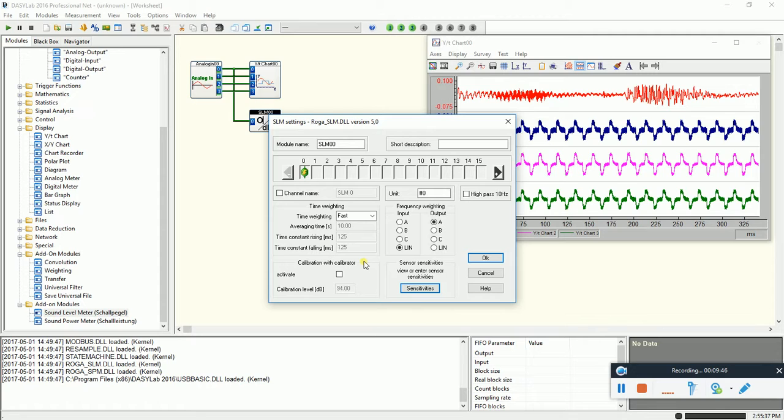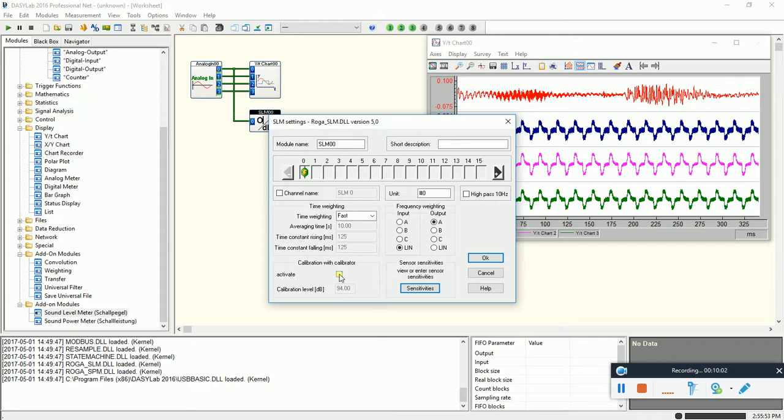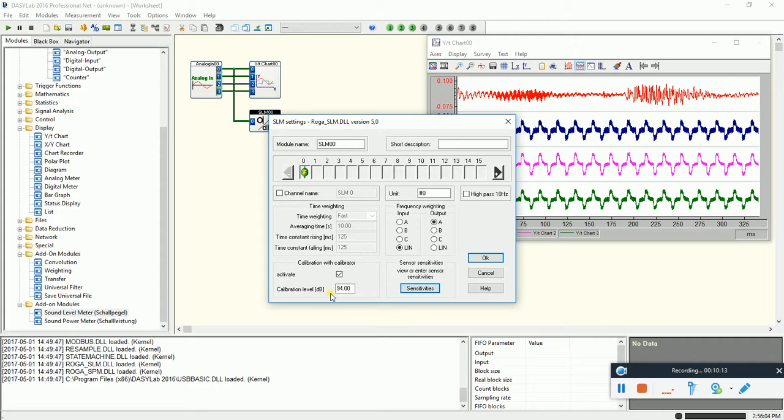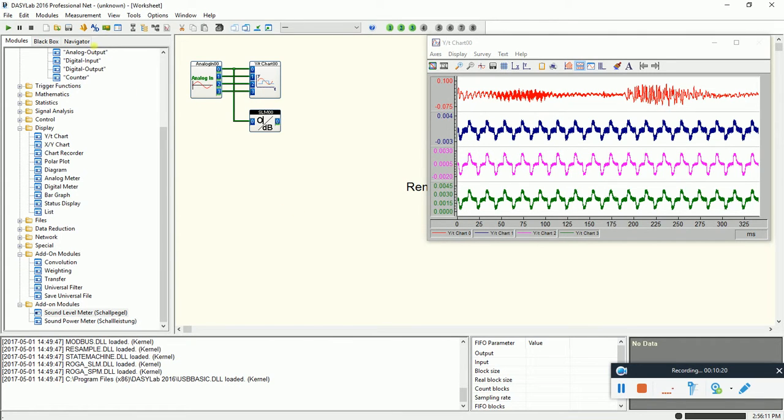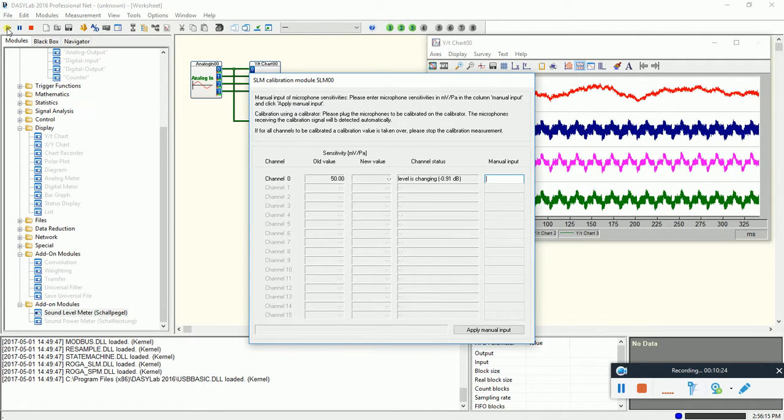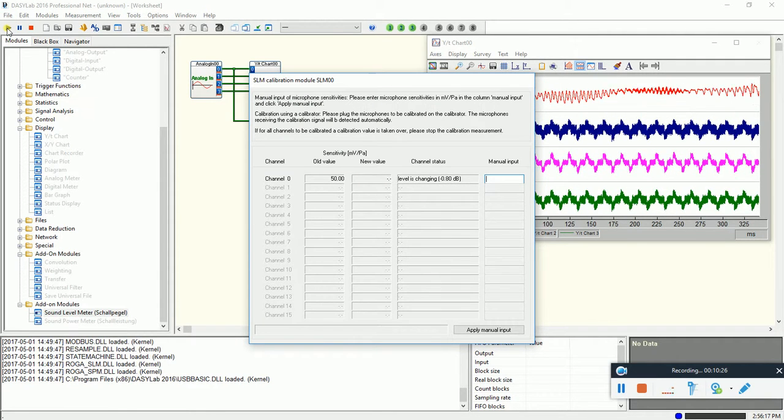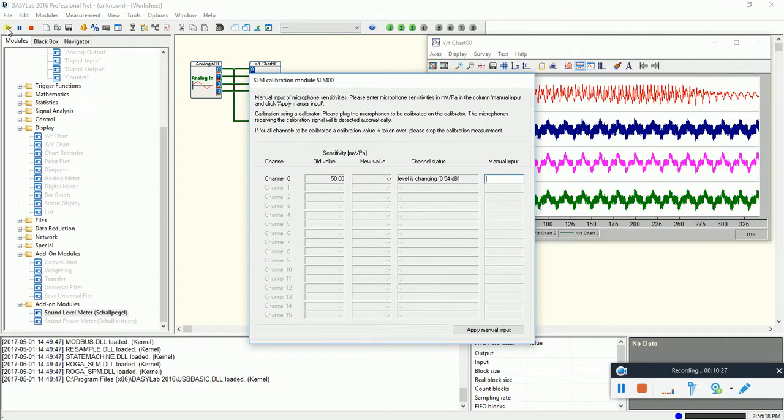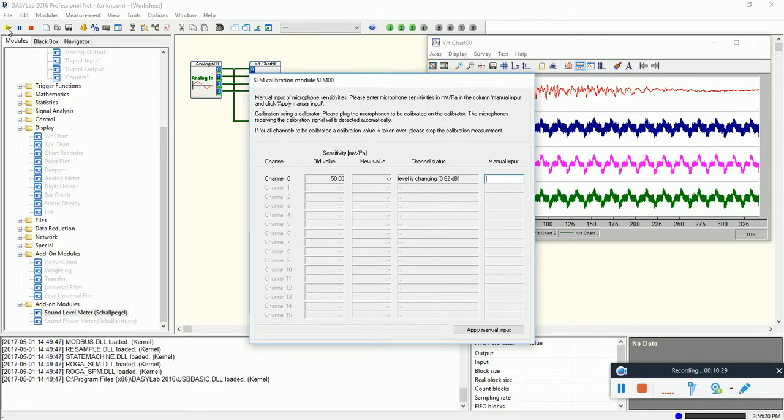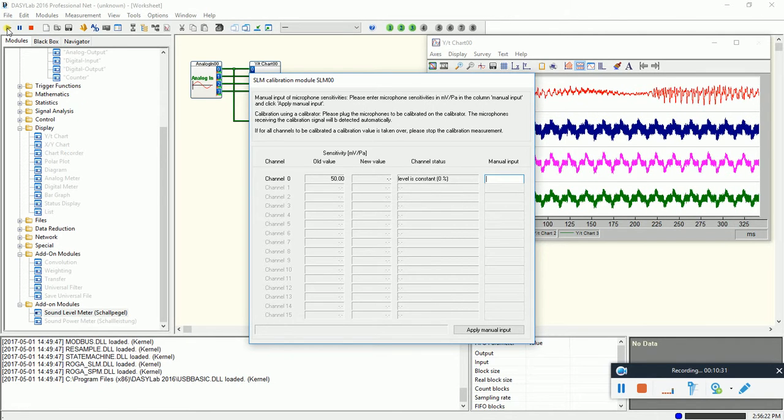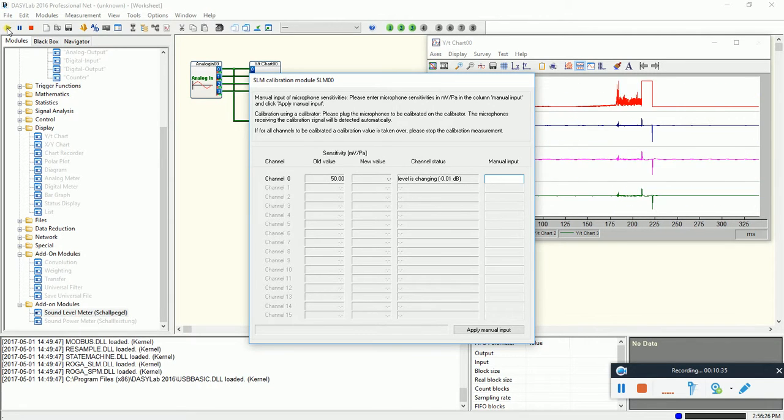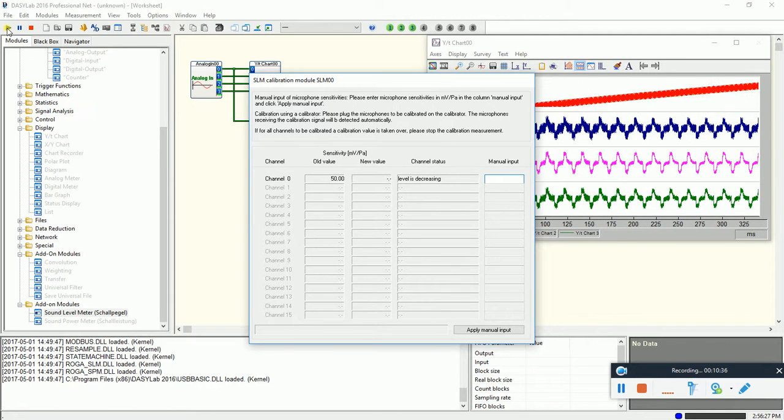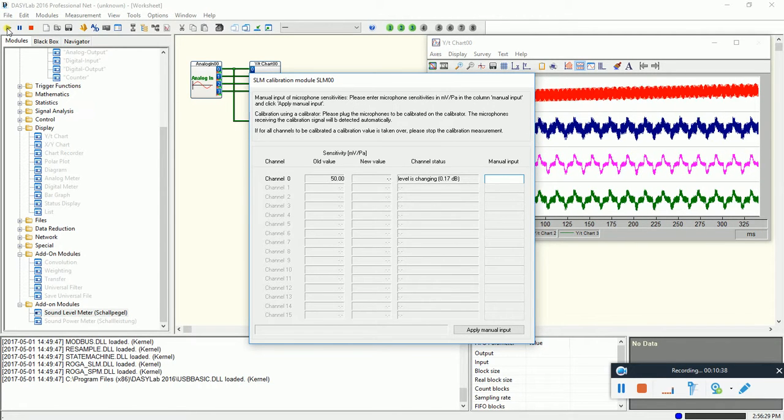So next, I have here a sound calibrator with 94 dB at one kilohertz, means one pascal sound pressure, and I like to execute now here the calibration. So the sound level meter, the calibrator have 94 dB, now I say okay. Now I have to start the measurement. Now he's waiting for a constant signal. So now I put the microphone into the calibrator. So now the signal is coming.